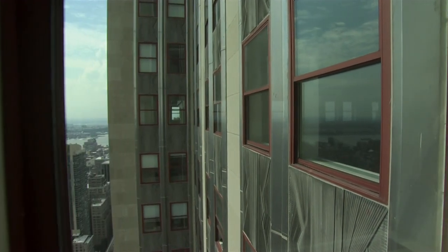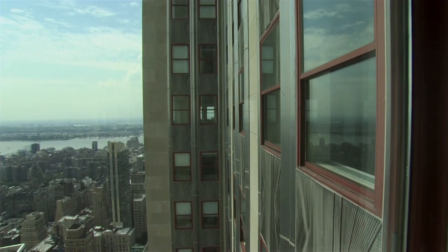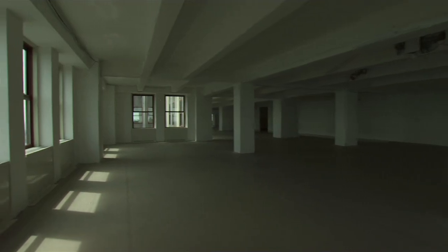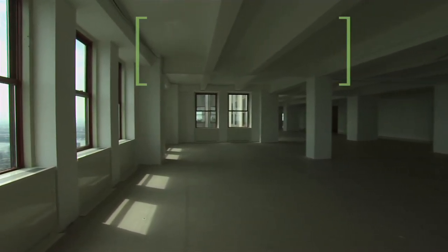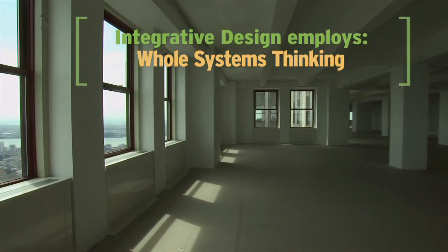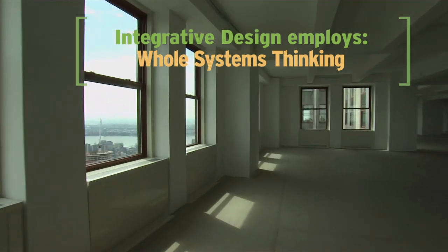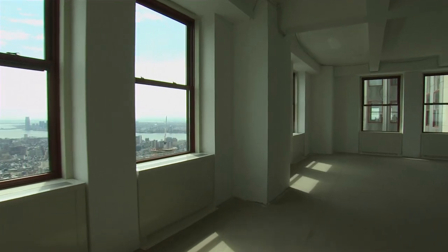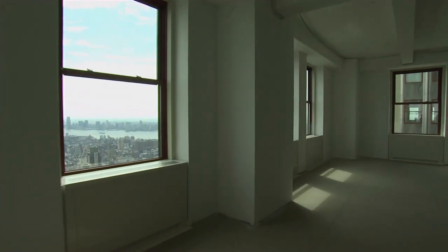By changing the building envelope insulation, both through the windows and against the walls themselves, it lowers both the heat and cold loads on the building. The way we as engineers like to look at it is what we call interactive effects. When we think about, well, the windows are going to do some good, well, yeah, they'll save energy, but more importantly, they'll make our system smaller. Our heating system is smaller, our cooling system is smaller. That optimization is much different than just what's the energy savings from a better window.